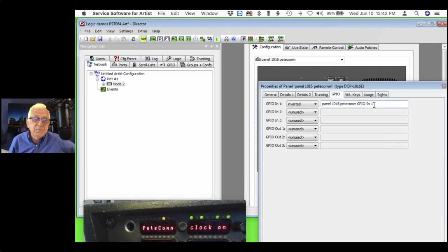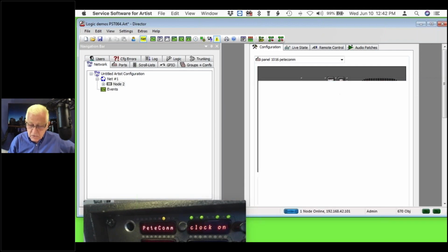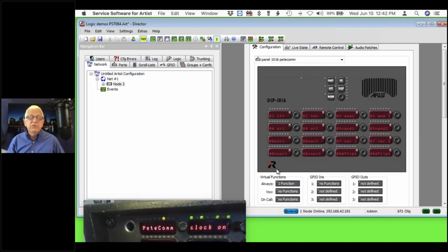So then we put this same relay button here into a relay that was plugged into the power of the UPS. As long as the UPS was powering the relay, its normally open contacts were closed, and its normally closed contacts were open, and we were sensing that the UPS was good.